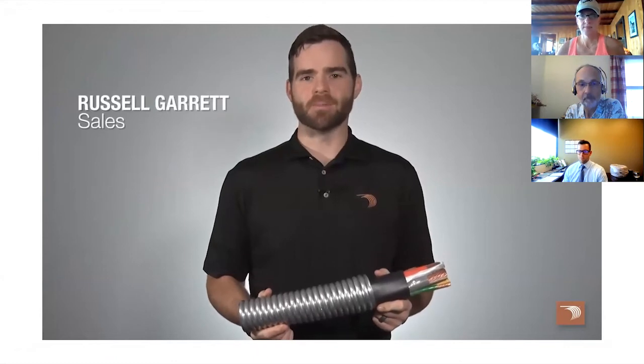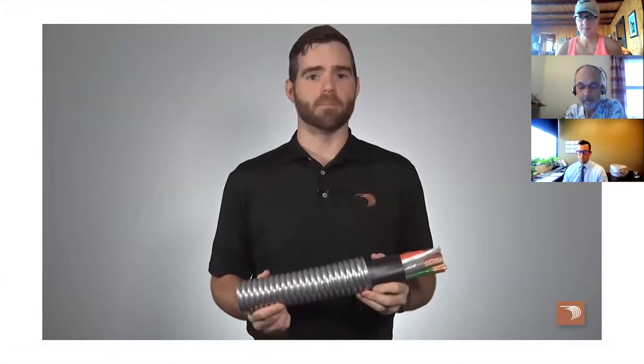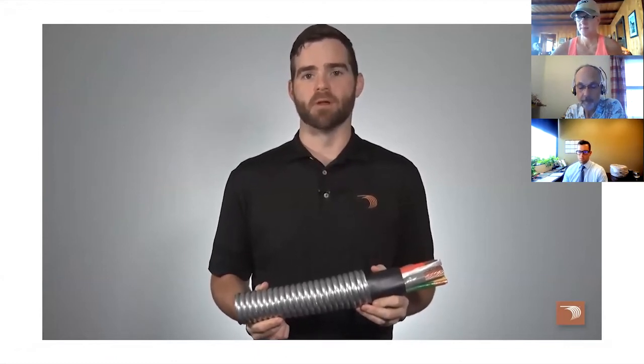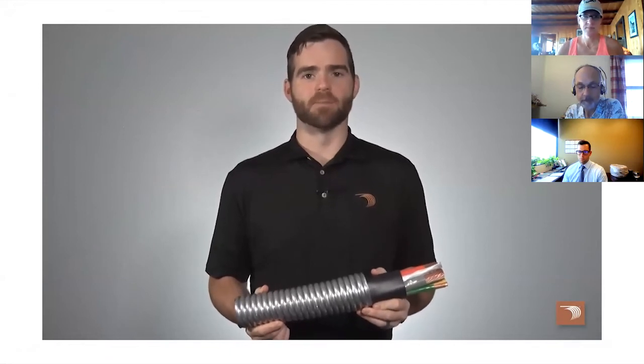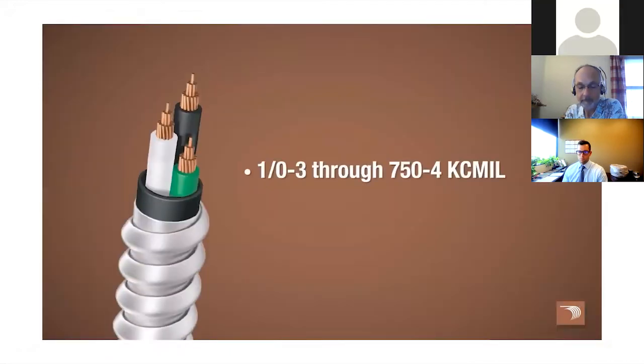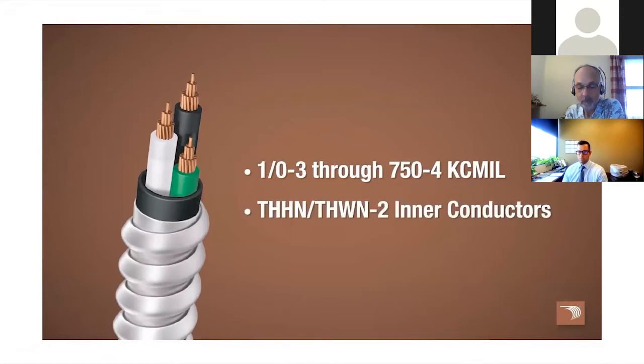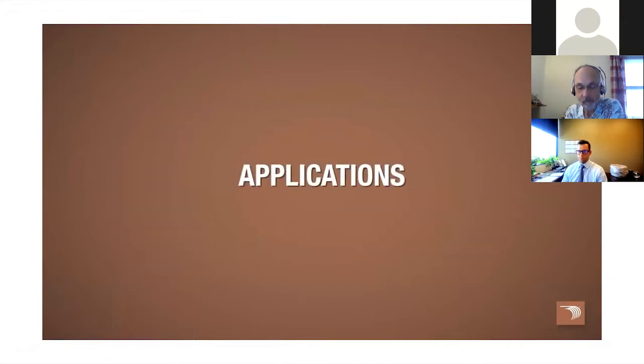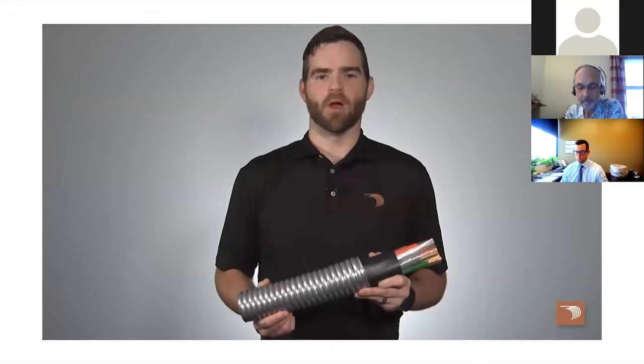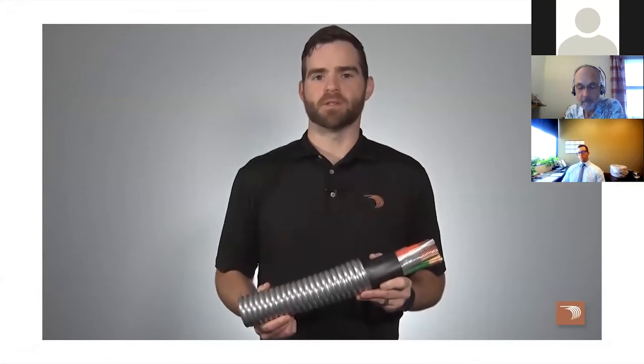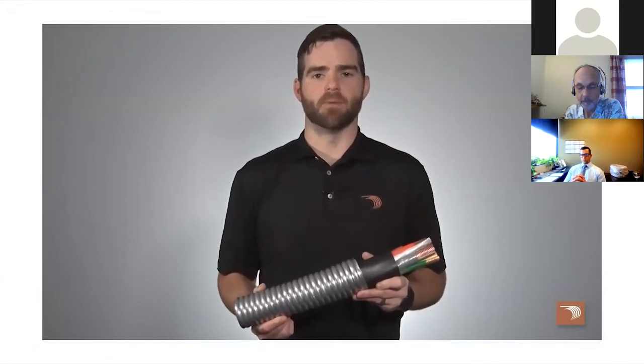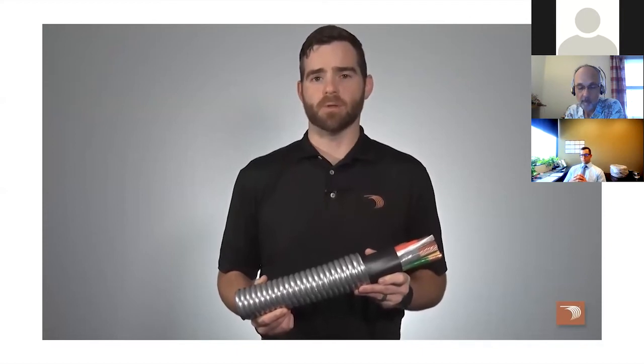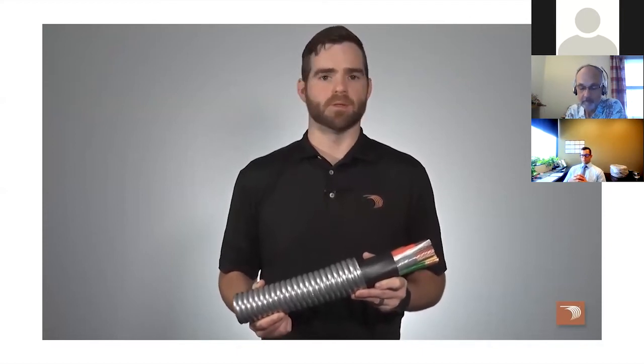Encore WIRE's new vertical run MC cable combines metal-clad and PVC-sheathed inner binder material to make a durable yet flexible cable assembly. We offer it in sizes 14 through 750 kcmil with THHN/THWN-2 or XHHW-2 inner conductors. Vertical run MC cable is suitable for installation in locations where traditional MC cable is installed and where extra holding power is desired for vertical applications.